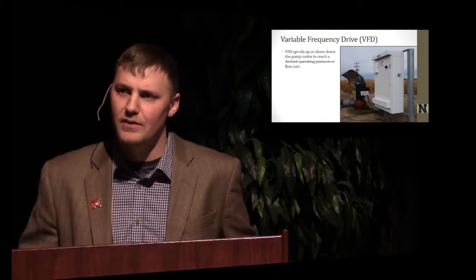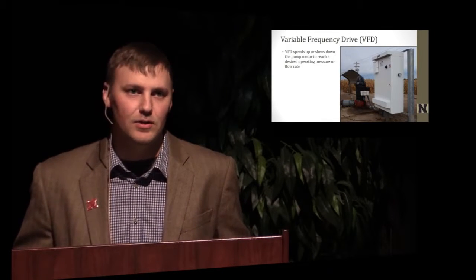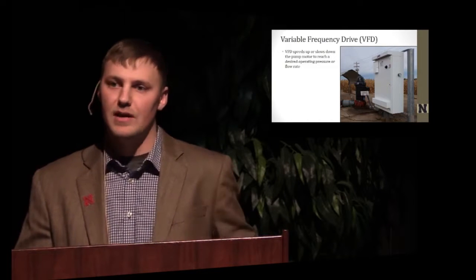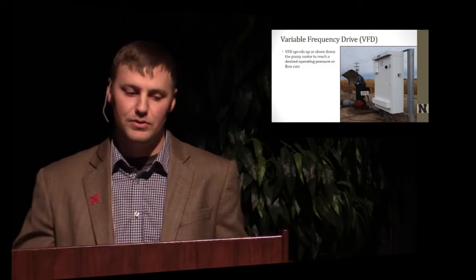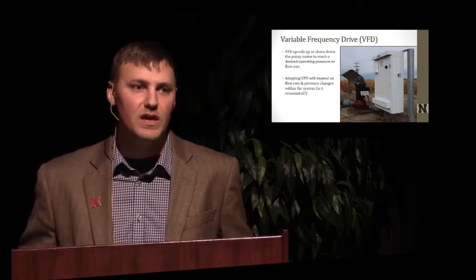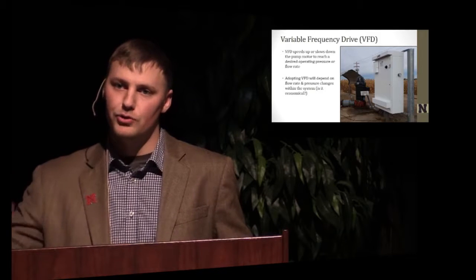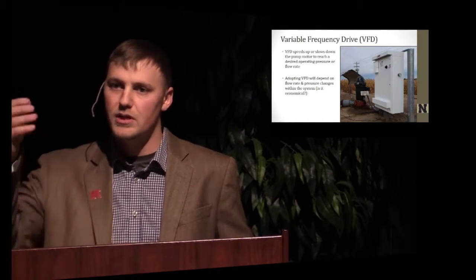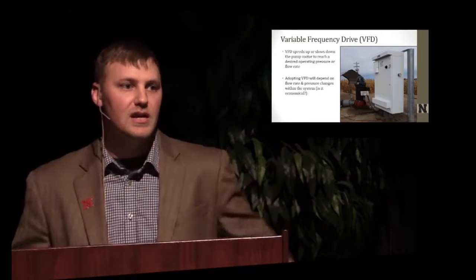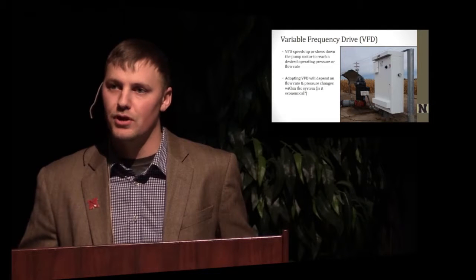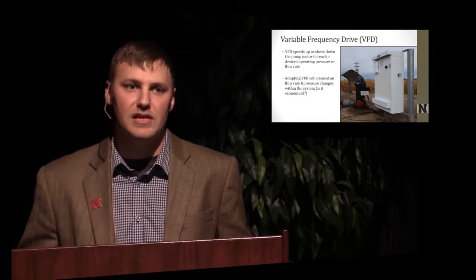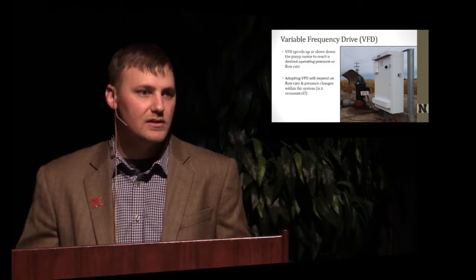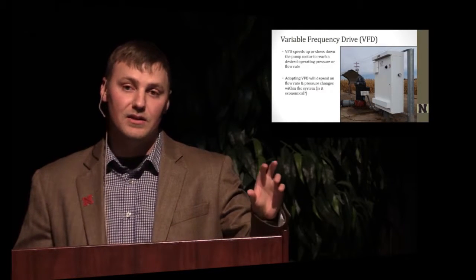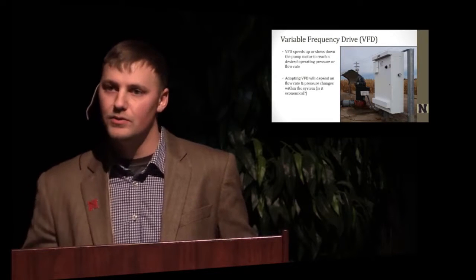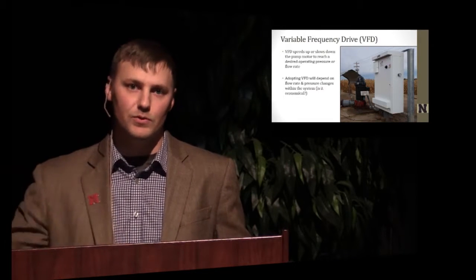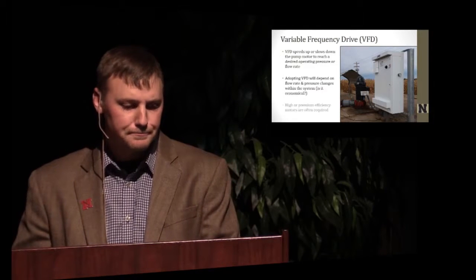One note I do always like to bring up is variable frequency drives. This is a technology that has developed over the years, and it allows for the opportunity for variable rate irrigation depending on the magnitude of change of pressure or flow rate. As you can imagine, if we start shutting off a large grouping of sprinklers on our irrigation system, we will drop the flow rate, which will cause the pressure to increase, and that will be unnecessary pressure on our pumping plant that otherwise could be reduced to save energy expense. So the question oftentimes is not necessarily a physical one, but rather an economical value of doing this, unless we get to extreme levels where we have over-pressurizing of our systems.